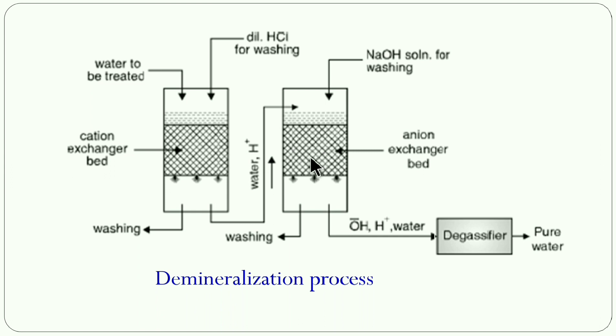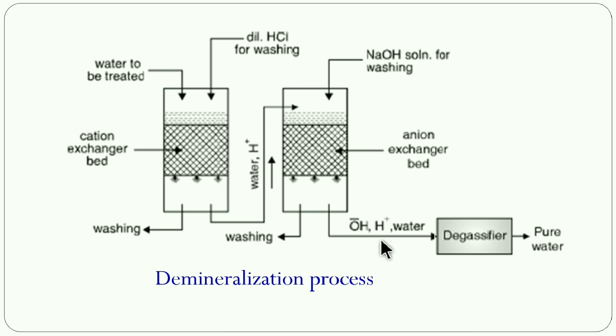The anion exchanger resin releases OH⁻ ions in exchange for the captured anions. The water coming out contains H⁺ and OH⁻ ions only, which combine to form pure water. All cations are captured in the first bed and all anions in the second, so no impurities remain. This water can then be passed through a degasifier for removal of any gaseous impurities such as CO₂ or O₂, yielding pure water of distilled quality.